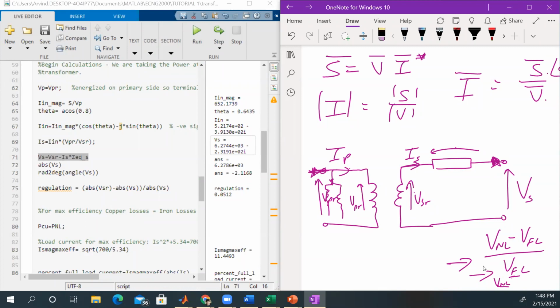So this value on top would remain the same. The full load voltage, of course, would be lower. So if you use full load voltage, your regulation would be worse because you're dividing by a smaller number. So you're going to get a bigger percentage regulation, which means a bigger fluctuation in how much the load voltage drops for the load. And for transformers, that is the main mechanism through which the utility will regulate the voltages on the system.